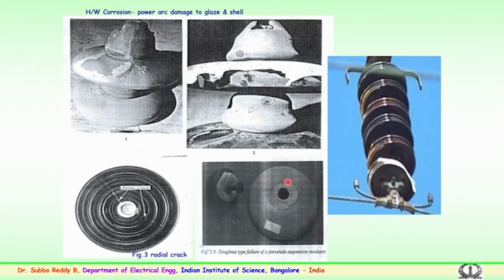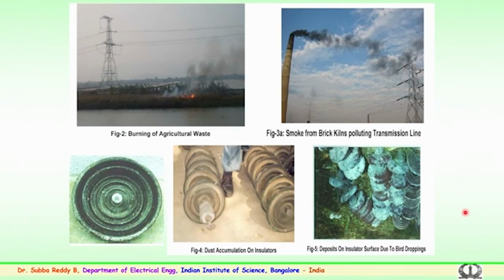This particular figure shows the cap and pin getting detached, which is known as a donut type of failure, where the material detaches itself from the ceramic unit over a period of time. This is because of the lightning over voltages the insulator string has seen in the field, where the insulator shed could be shattered because of the over voltages or the very sharp rise in voltages. Whatever we have seen are natural things which have happened.